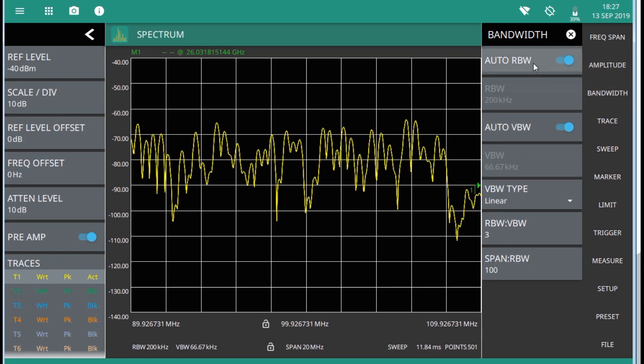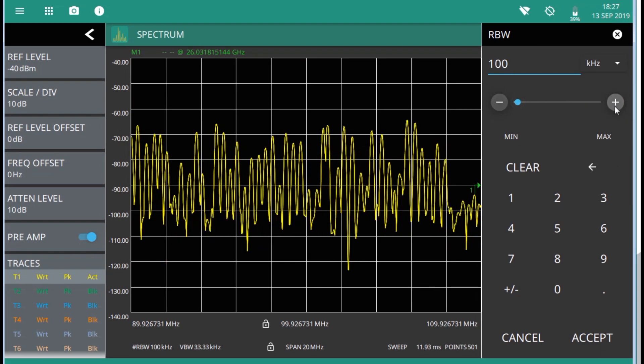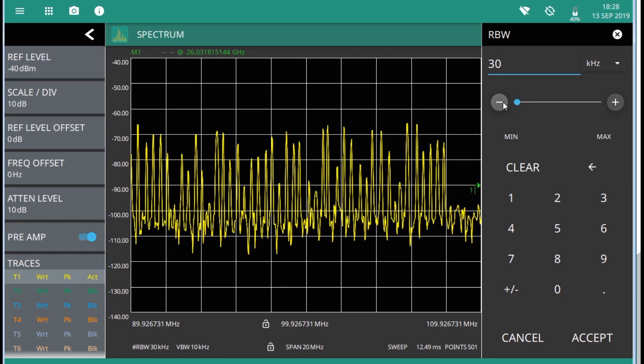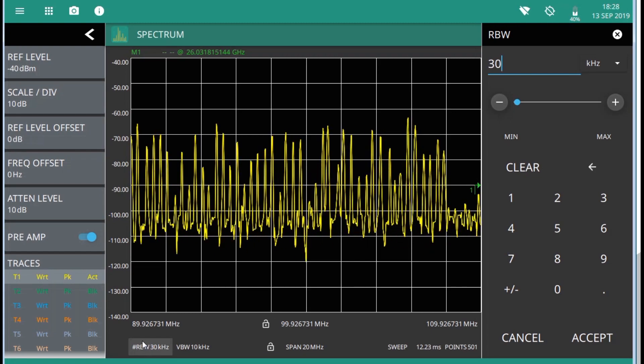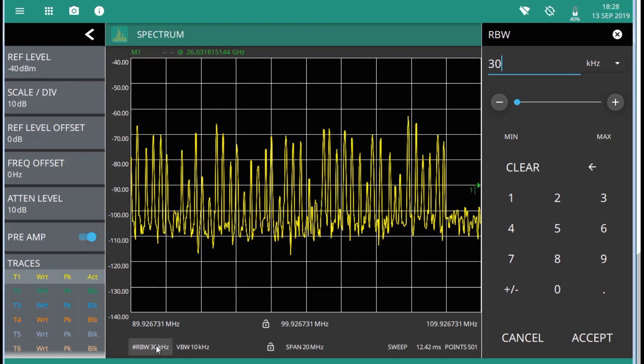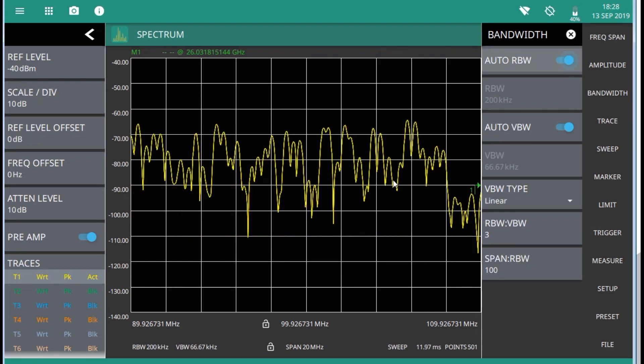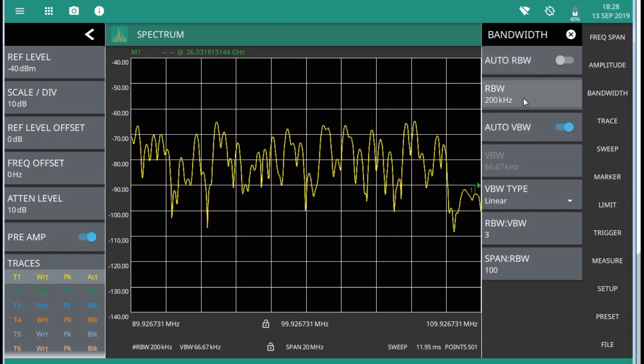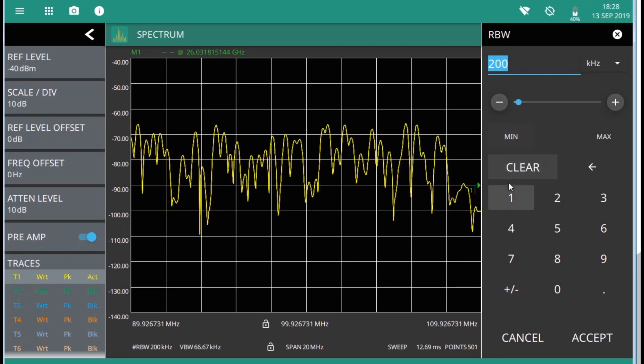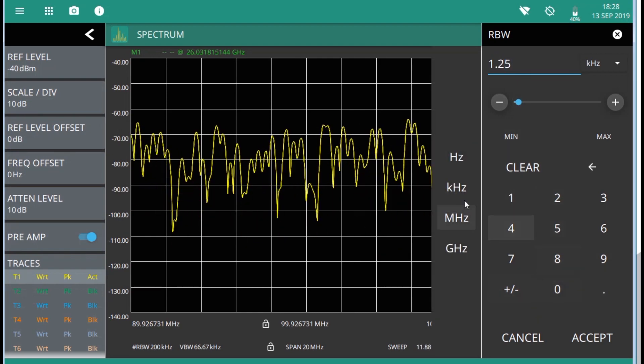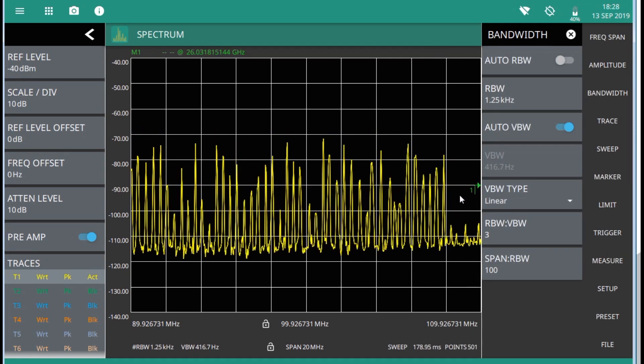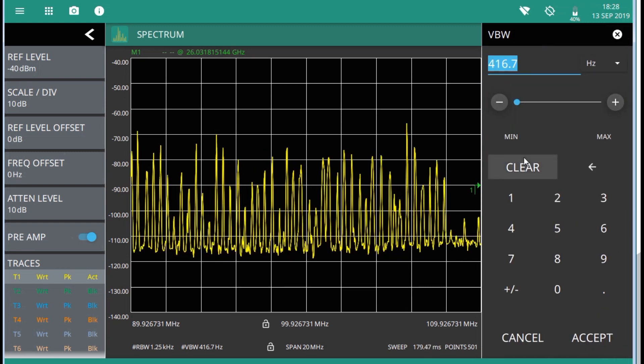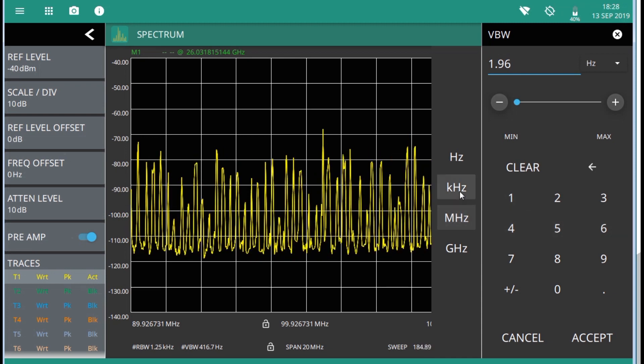Move on to the bandwidth and RBW, I can change this in a 1-3-10 fashion. The hashtag in front of the value indicates that I am in manual mode now. As example, I can switch back to auto mode. Basically, you can use almost any arbitrary value for RBW if you have particular settings that you prefer to work with, as example 1.25. And same thing with video bandwidth. You can set this to nearly whatever you want, 1.96 kHz.